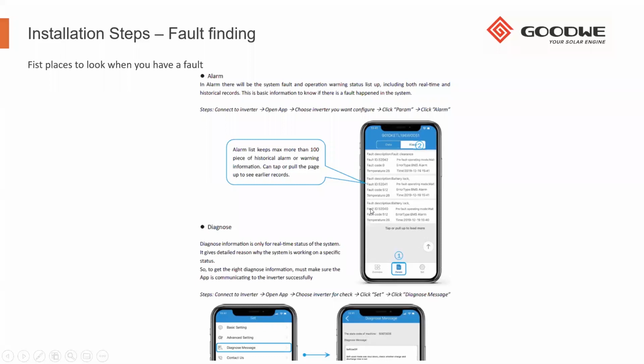One thing to keep in mind is that we are constantly, especially on the newer firmwares of the inverter, updating the error codes that can be viewed and improving the fault finding for us. Very often the app may not have that, and then you'll find a fault code 0. A fault code 0 just means the app itself doesn't have a definition yet for that fault code.